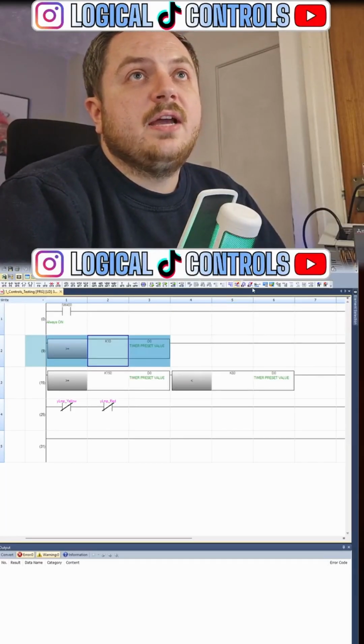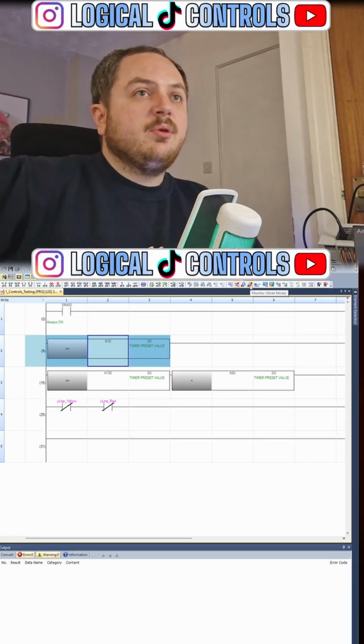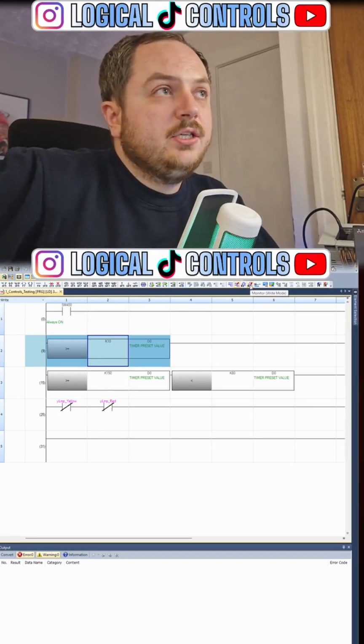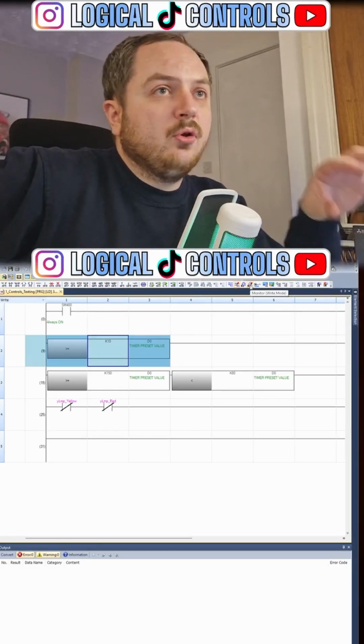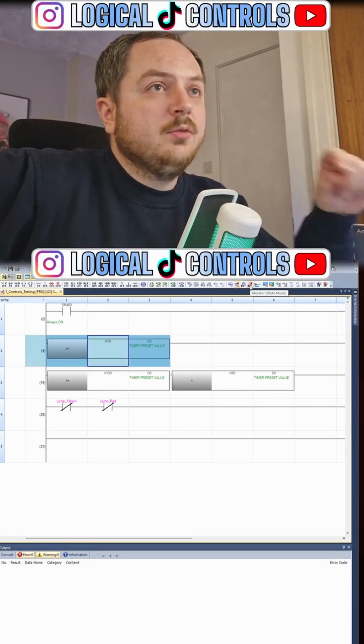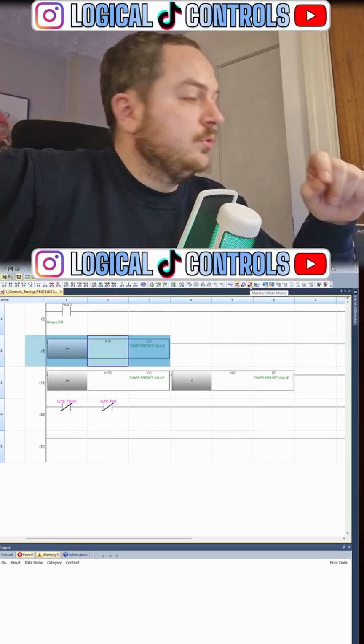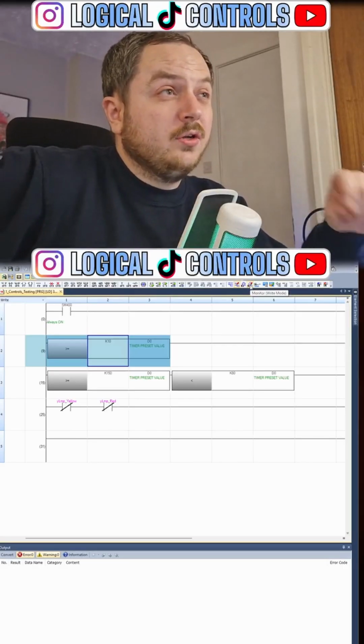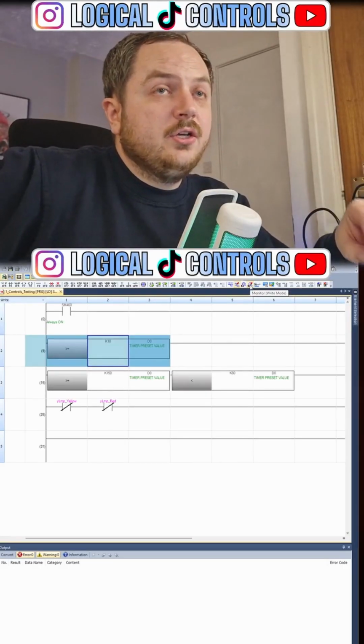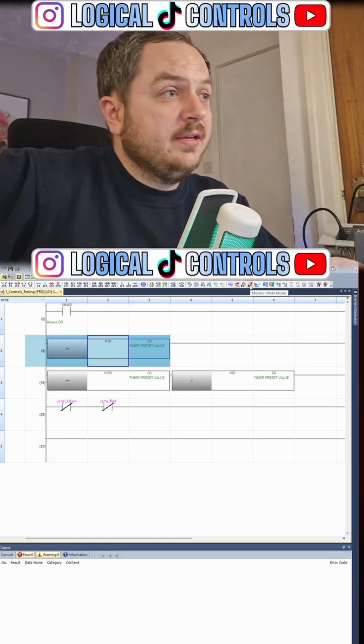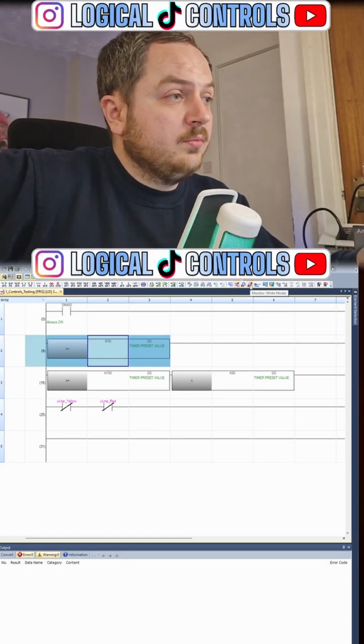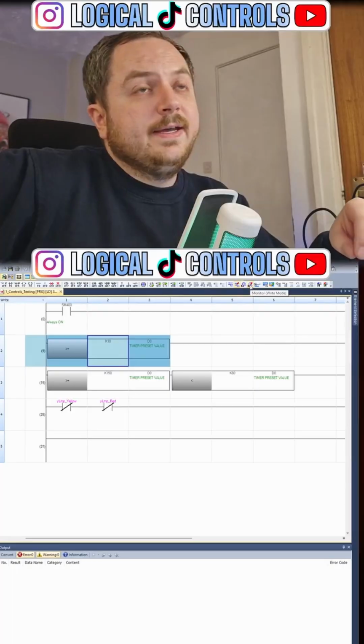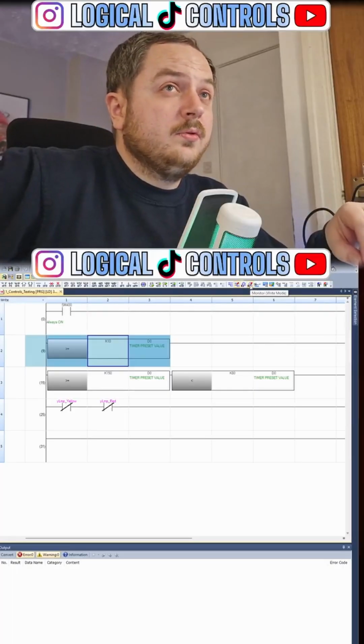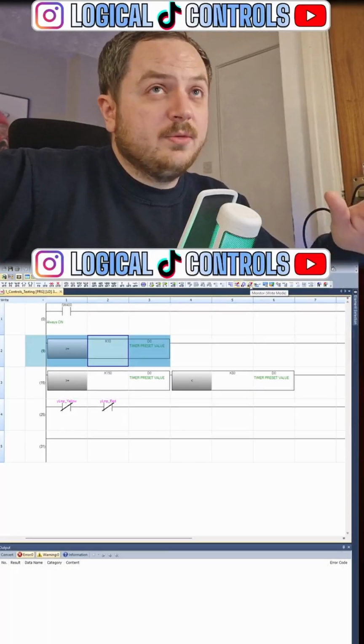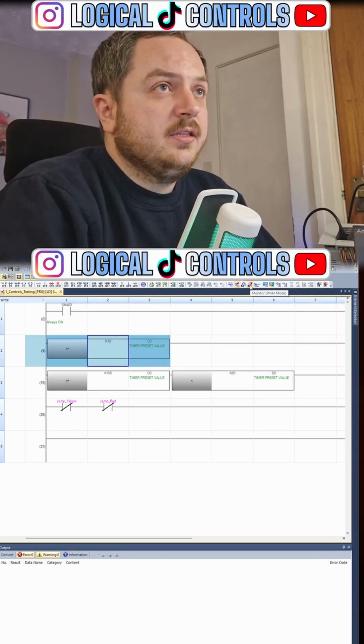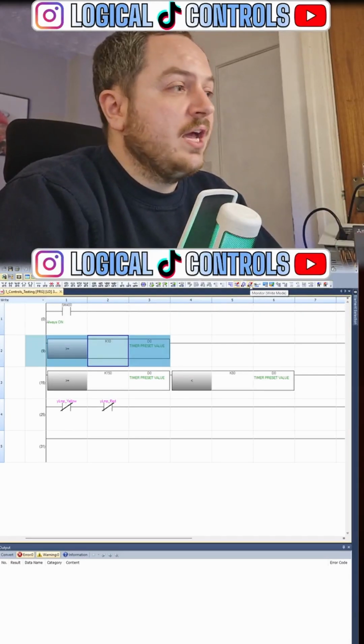In fact, let's do a live change. So when you're programming PLCs, you can do it one of two ways. You can basically write the program offline, then download it to it. The problem with doing that is you have to put the PLC into stop. So if you're working on a live machine in a factory, you're going to have to put that into stop. You might mess something up. You're going to definitely stop the process of whatever it's doing. So a lot of people, if you're working on a working machine, or the PLC basically can't go off, you do a live change.